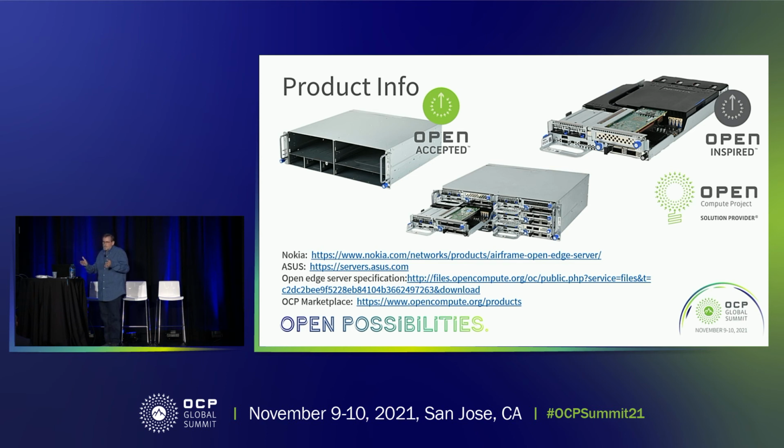This would be useful for a 600 millimeter rack, so you don't have to have the 1,000 millimeter or the 1,500 or 2,000 that some of those larger servers require. This is designed for far edge deployment where something may be mounted on a wall or in an outdoor enclosure. On the marketplace, we have a couple of outdoor enclosures for this unit that are sealed, heated and air conditioned as well. Even though it has a wide temperature range from NEBS, it also has environmental control.